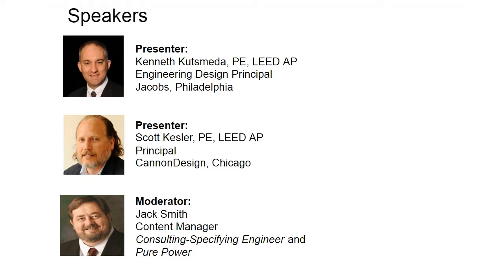Yeah, I guess I need to elaborate on that. So basically N is what they call need. So it's basically to meet the need of your load. So you basically have the generator's size to meet the need of your load. And then N plus 1 is need plus an additional one. So if you need 3 generators to meet the load, N would be 3, N plus 1 would be 4. So you have the 3 to meet the load plus an additional one should any of those fail or you need to take one out for maintenance.